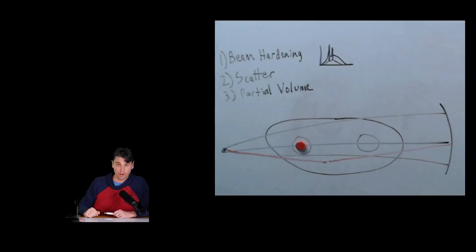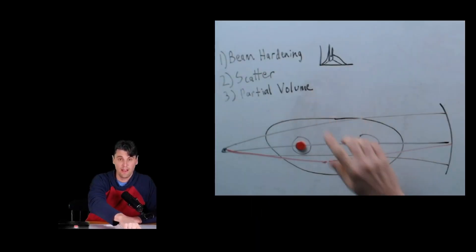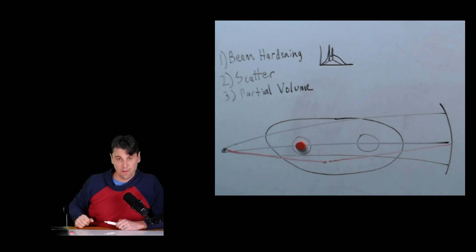Number three is what we call partial volume artifacts. The idea here is we're actually dealing with a nonlinear process in Beer's law, and we do a logarithm of the data in order to make it linear. But in the case where there's this significant amount of attenuation here and it's changing rapidly, that can cause what we call partial volume artifacts.